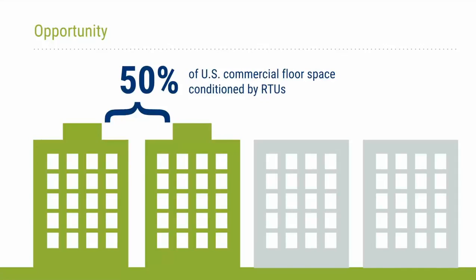So as you heard from Kevin, in 2011, to stimulate the market with higher performance units, Department of Energy Building Technologies Office issued a challenge to manufacturers to build a unit that is 50% more efficient, based on IEER. And IEER is basically an integrated energy efficiency ratio. It could be viewed as a seasonal efficiency measure, as opposed to energy efficiency ratio, which is a measure of efficiency at a single indoor and outdoor condition.